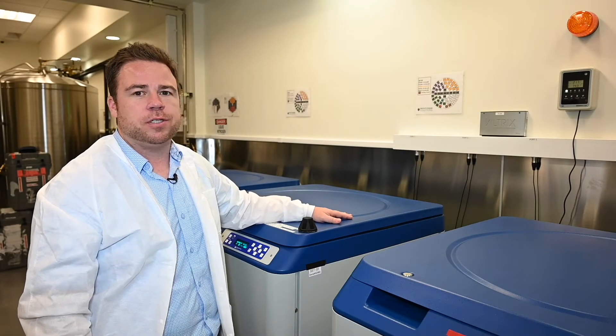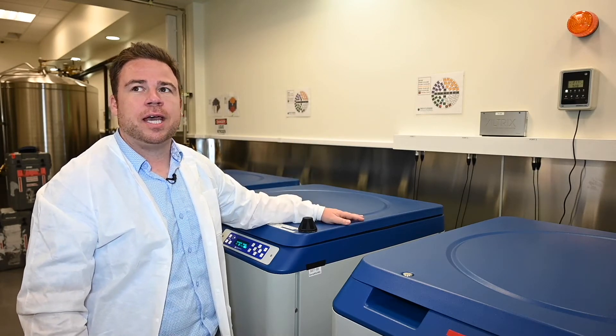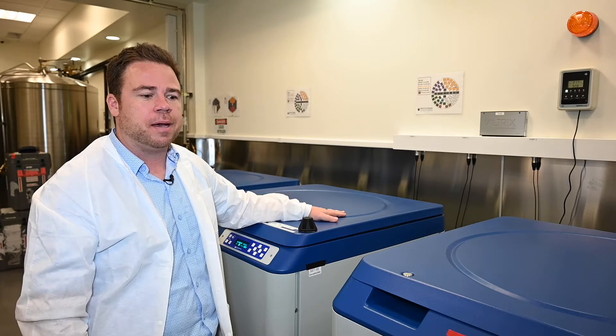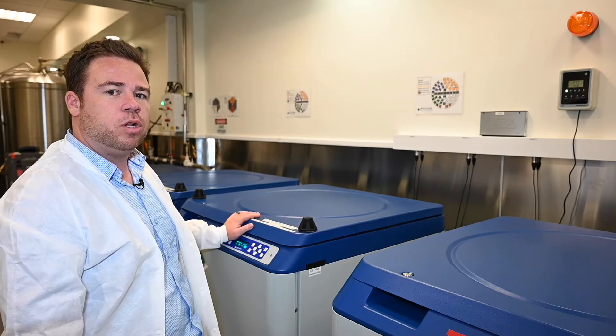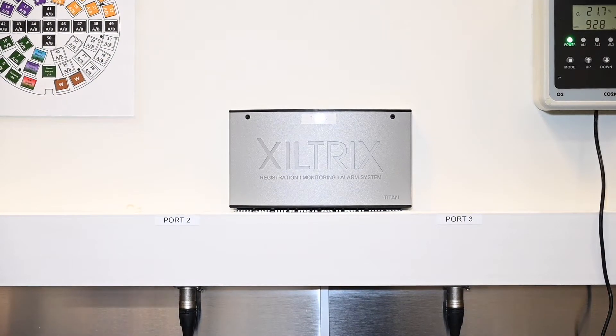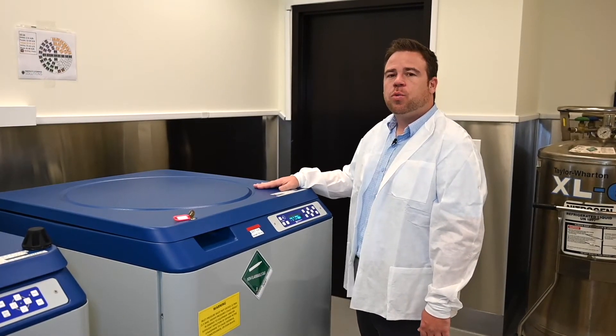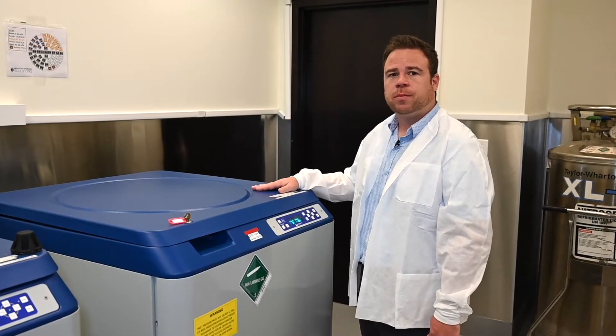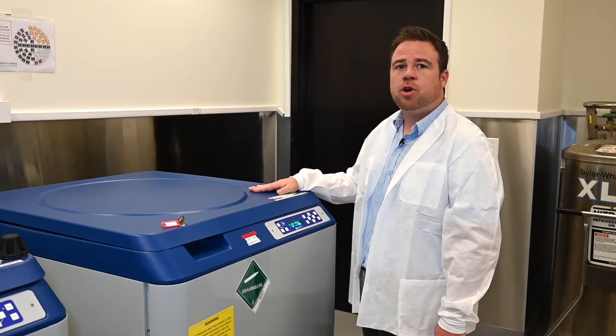Safety is of the utmost importance to us here at Fertility Storage Solutions. We have multiple layers of safety. We have video surveillance 24 hours a day inside of this room that I can access at any time. All of our tanks have at least two alarms on them. This tank right here has an alarm built into the tank that will go ahead and alert us. The next alarm system is our real-time monitoring, which is our Xiltrix alarm — it has a probe that gives us real-time monitoring 24 hours a day. There is currently 26 inches of nitrogen inside of this tank. One of the nice things about liquid nitrogen storage is that it does not need electricity in order to maintain proper storage. Given any natural disaster or power outage, these tanks are good for many, many weeks without any backup nitrogen or electricity.